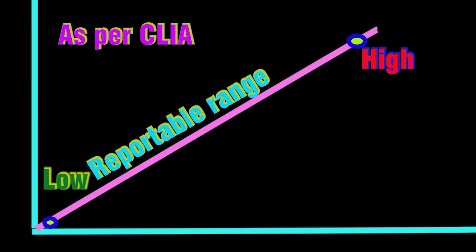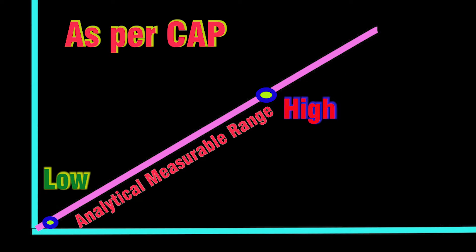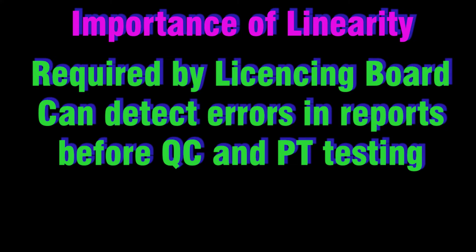Here, linearity is outlined as the relationship between the final analytical result for a measurement and the concentration of the analyte being measured. As per the College of American Pathologists (CAP), the analytical measuring range is the range of concentration of an analyte that a method can directly measure without any dilution, concentration, or other treatment.